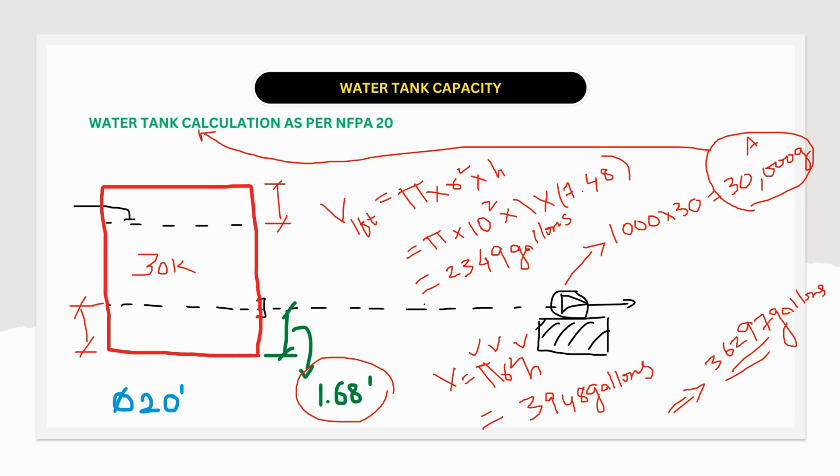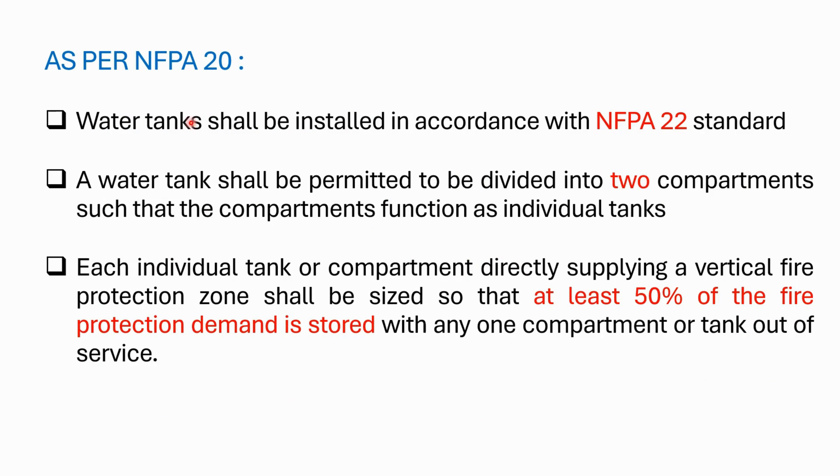In the market, I don't think 36,297 gallons water tank would be available. So we will consider 40,000 gallons water tank based on the standard tank size. We need to keep three most important points related to the water tanks as per NFPA 20. Water tanks shall be installed in accordance with NFPA 22 standards, and the water tanks shall be permitted to be divided into two compartments such that the compartments function as individual tanks.